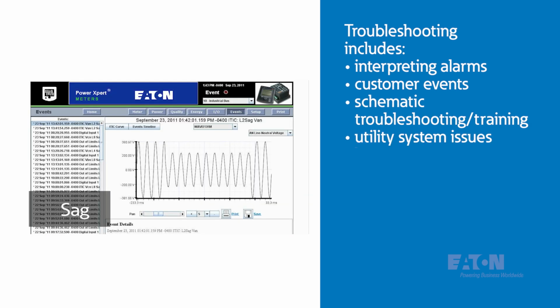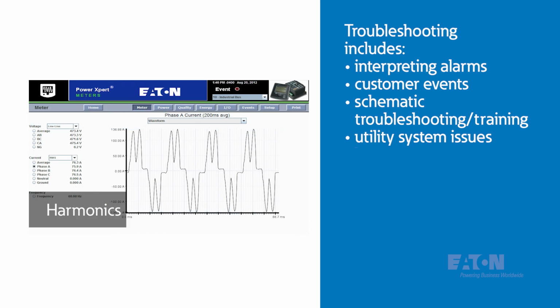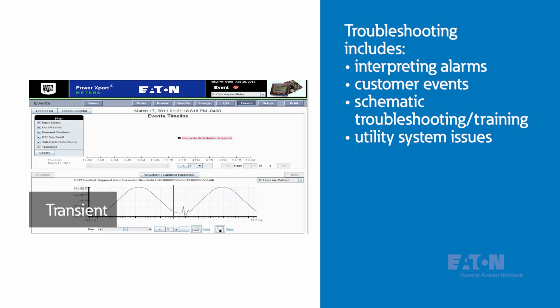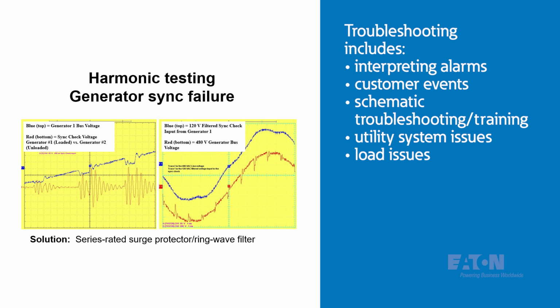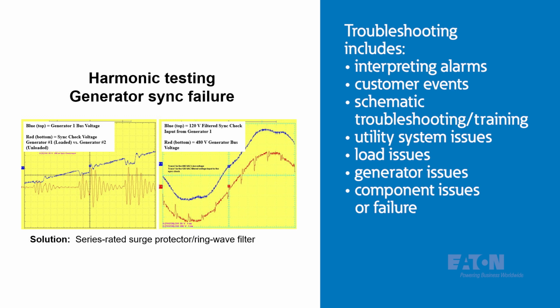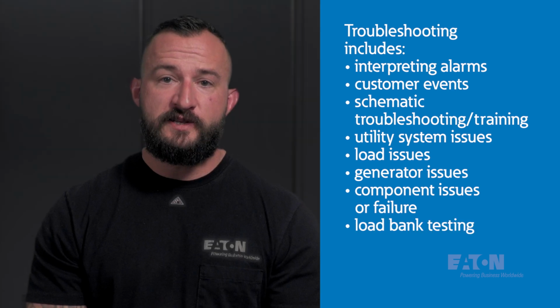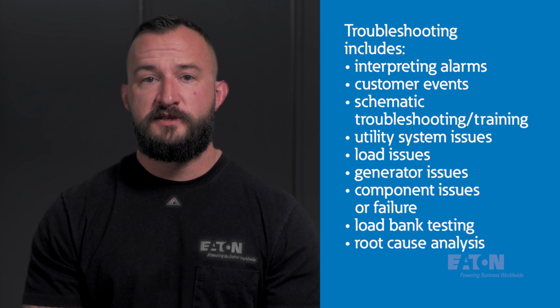We look at utility system issues like capacitor switching or voltage sags. We evaluate load and generator issues considering things like harmonics. We evaluate component failures within our own equipment. We do load bank testing to evaluate overloads and load steps. And finally, we always make sure to include root cause analysis to come up with a permanent fix to prevent reoccurring events.